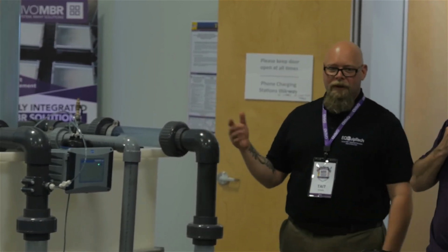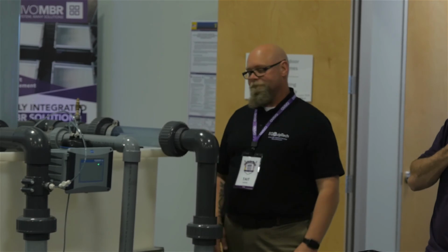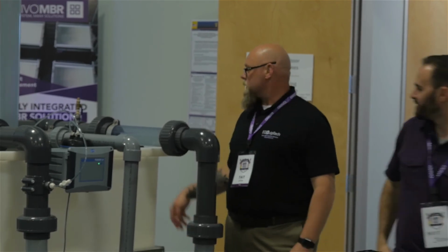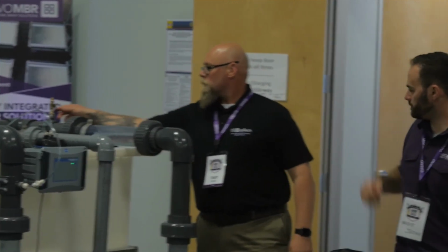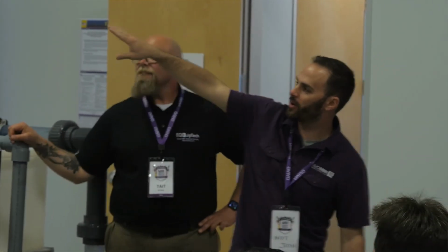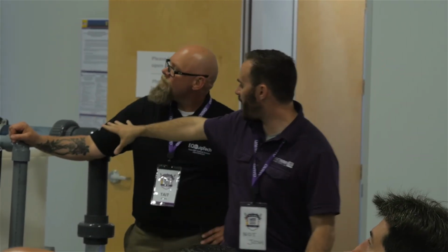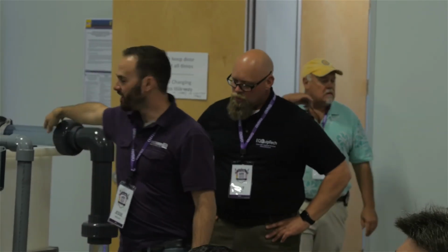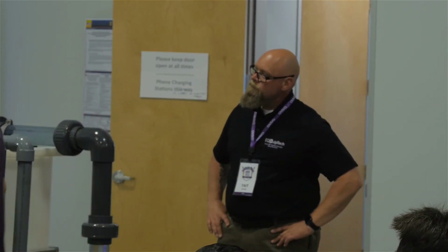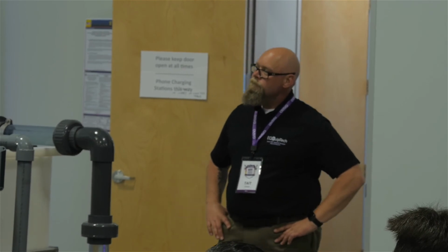Alright. So, yeah, bring it up, we'll see this again too. If we look at our trends up here, now he's closed it up. We just wanted it to relax again, but we're still holding this air in here. It's locked in here. If you find a small hole like that, suddenly you don't have a fight anymore when you show up in the morning. So it's really, really important.